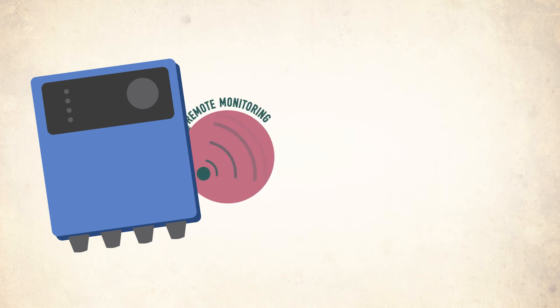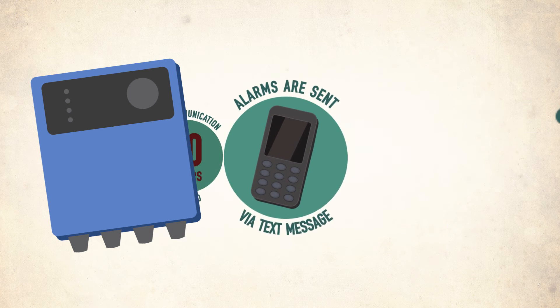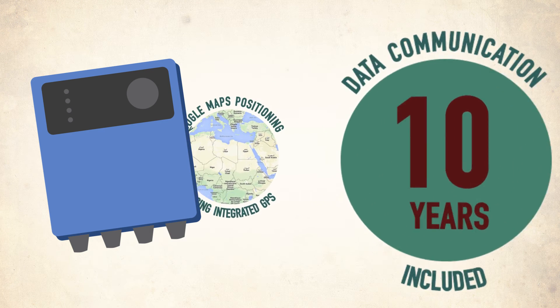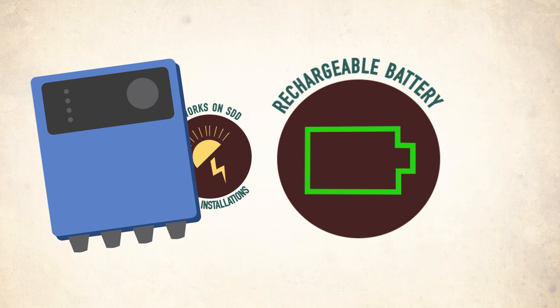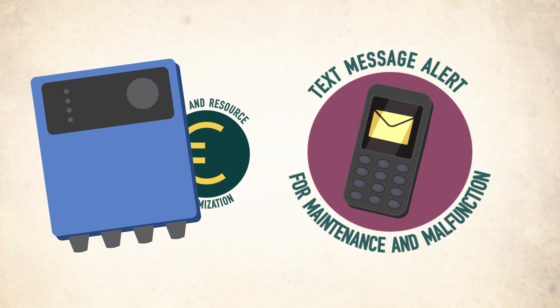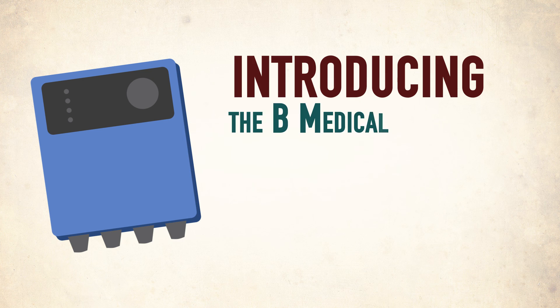The characteristics and main functions are: remote monitoring; data access over web — only cell phone network coverage is necessary to operate; alarms sent via text message; ten years of data communication included; Google Maps positioning using integrated GPS; alarms include temperature deviations and lid openings; rechargeable battery; works on SDD and AC installations; text message alert to user for regular maintenance and for refrigerator malfunction in real-time; cost and resource optimization. Introducing the B Medical Systems Data Logger.